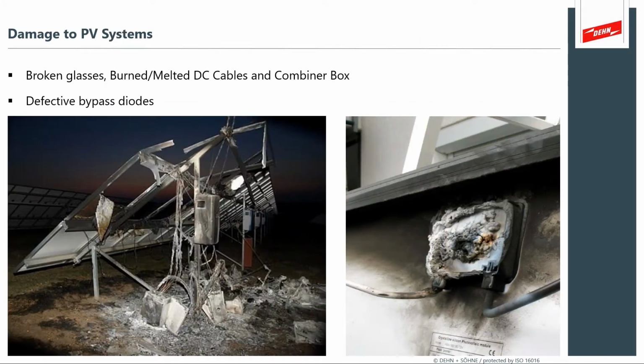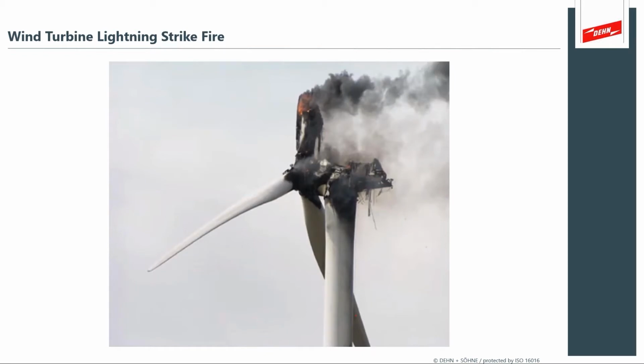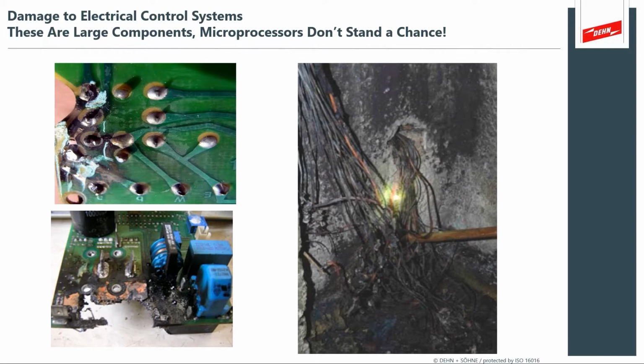Of course, there are other power generation facilities in the solar industry where it'll cause fire. You have direct strike energy going directly into the bypass diodes and converter combiner boxes. Wind turbine power generation facilities, of course, are a very, very exposed type of environment with these tall structures and the extensive collection area. Here you see a very expensive fire causing complete destruction of a power generation asset. The damage can take the form of much more subtle damage on circuit boards and, of course, wiring systems that would cause the complete failure of extensive wiring and interconnecting cable systems.